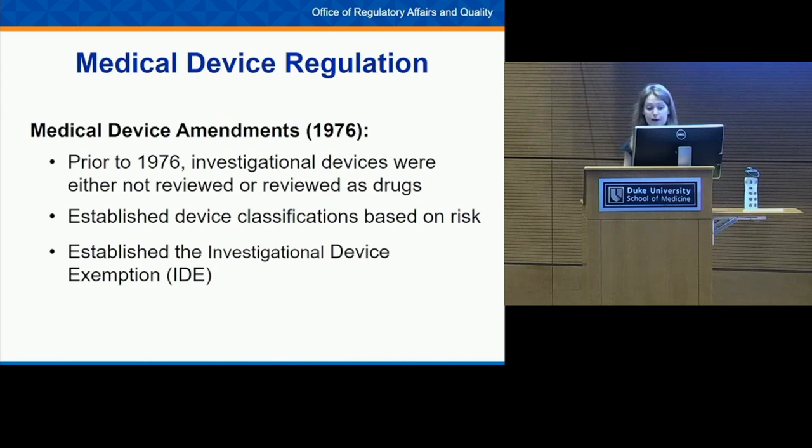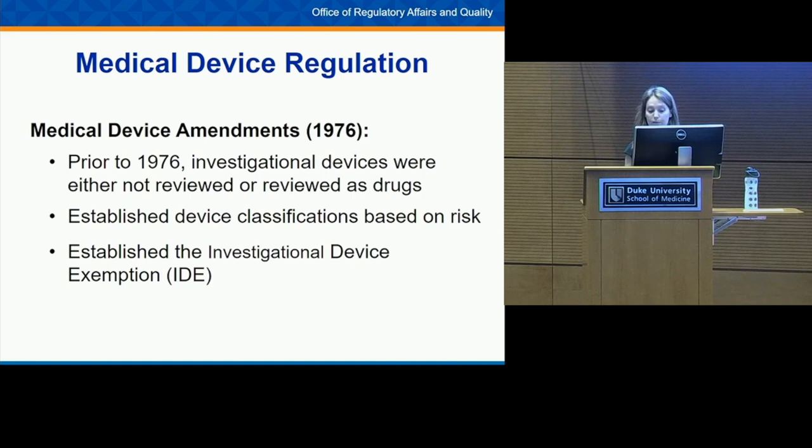Medical devices were not reviewed by FDA before going to market until 1976, when the Medical Device Amendments were passed. Before that, investigational devices were reviewed as drugs or not reviewed at all. These amendments established device classifications based on risk and also established the Investigational Device Exemption, which will be a big focus of this talk.